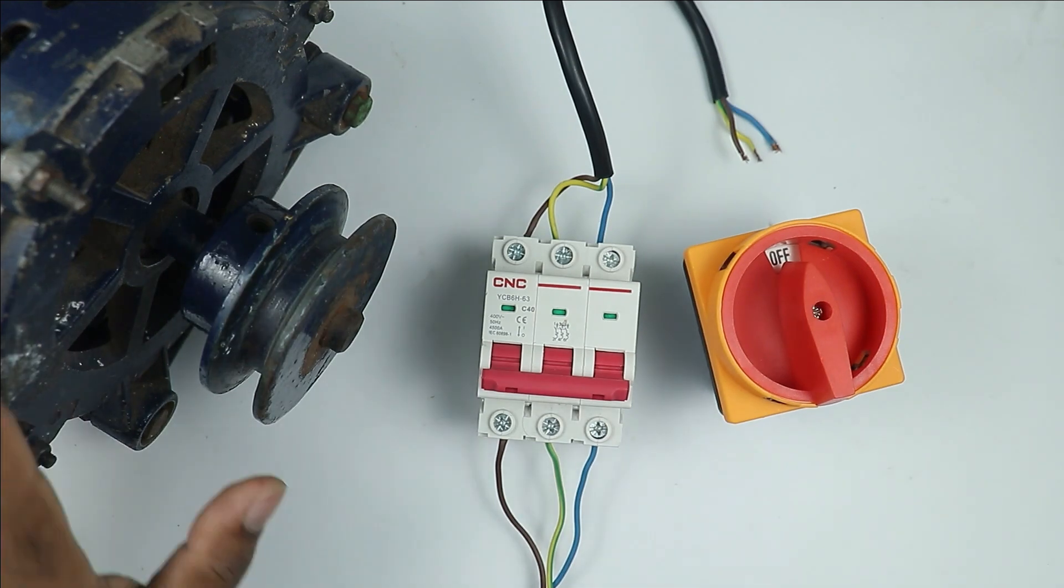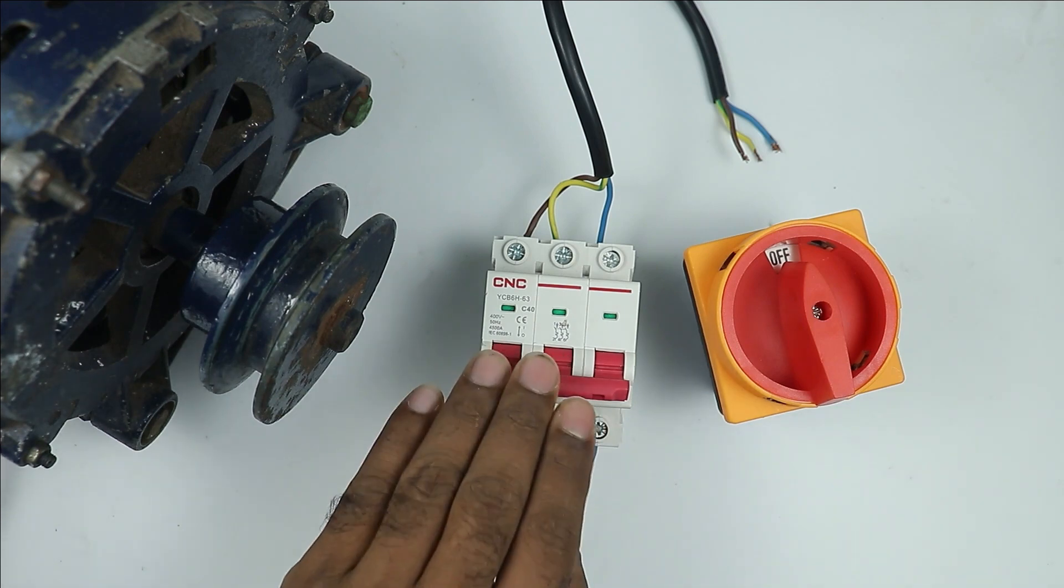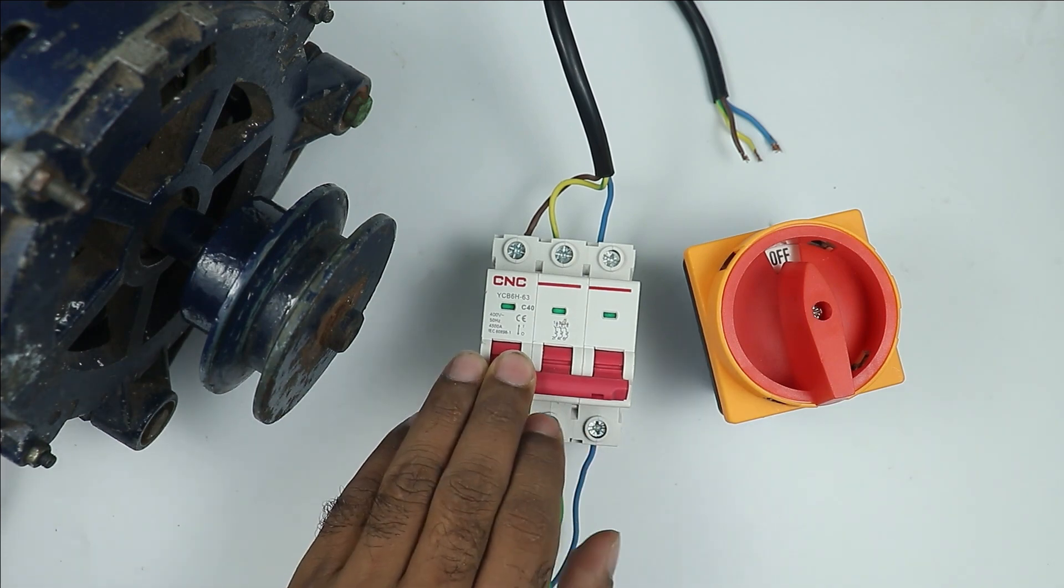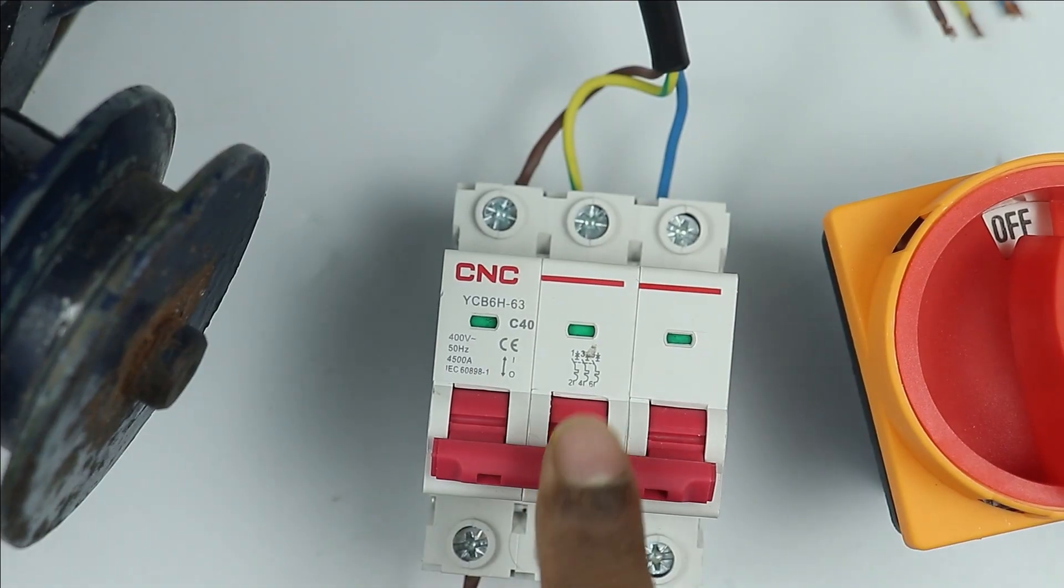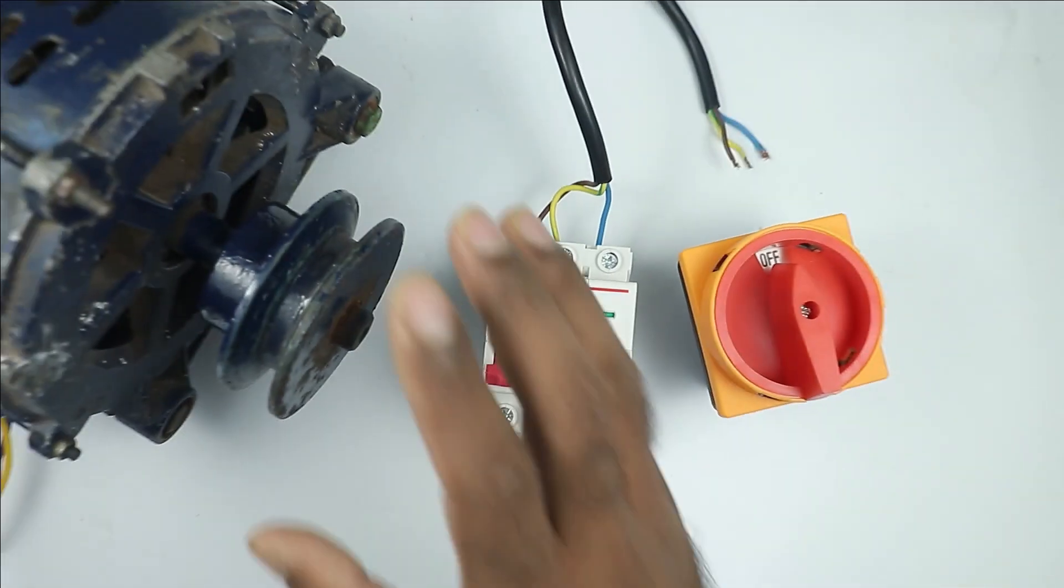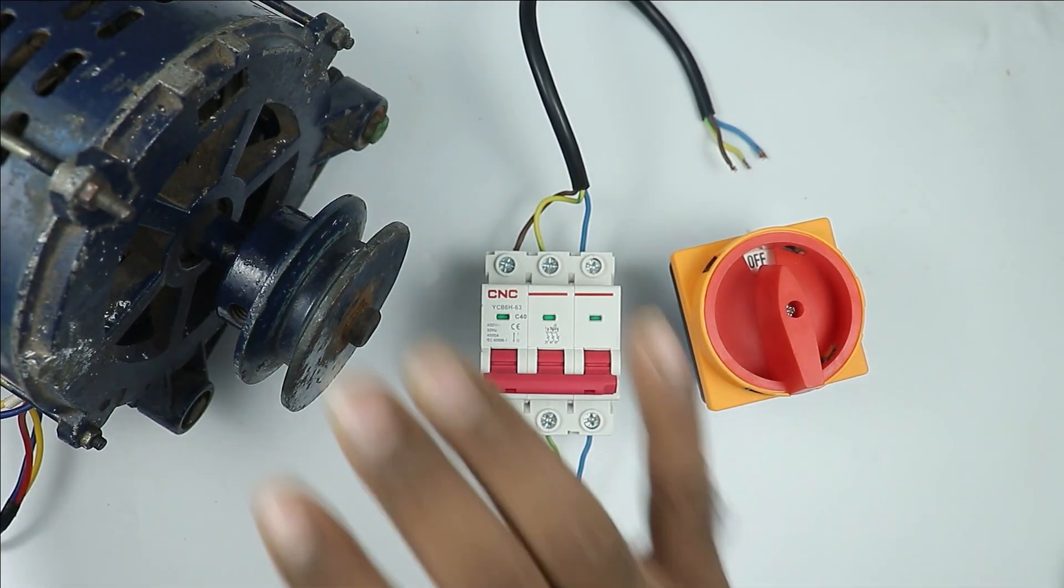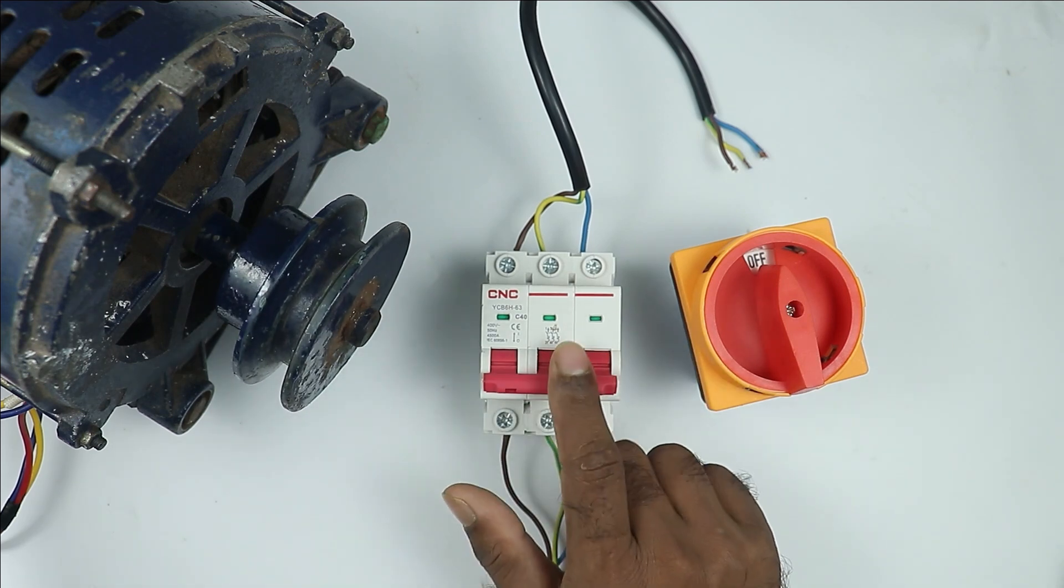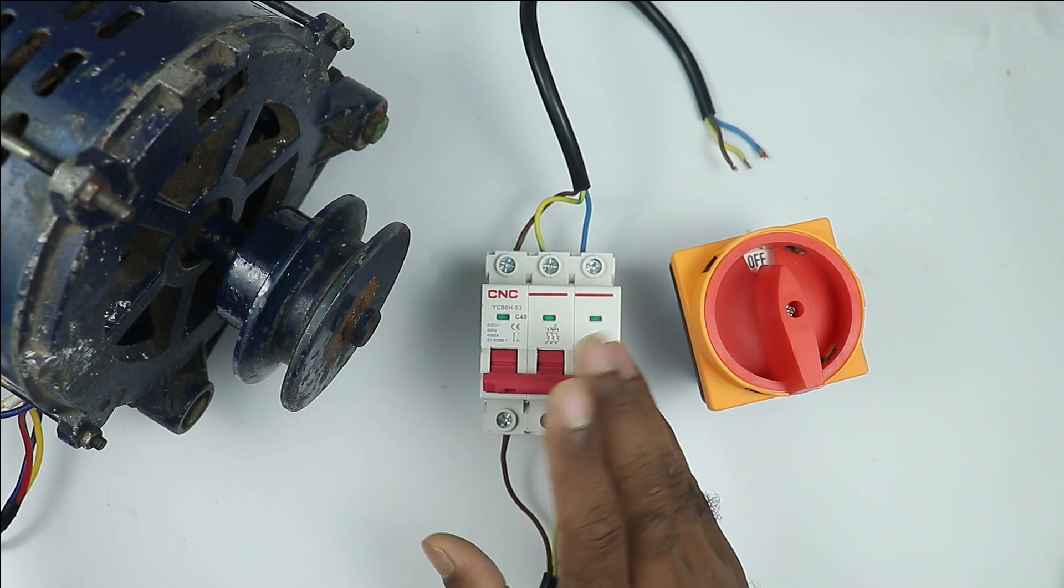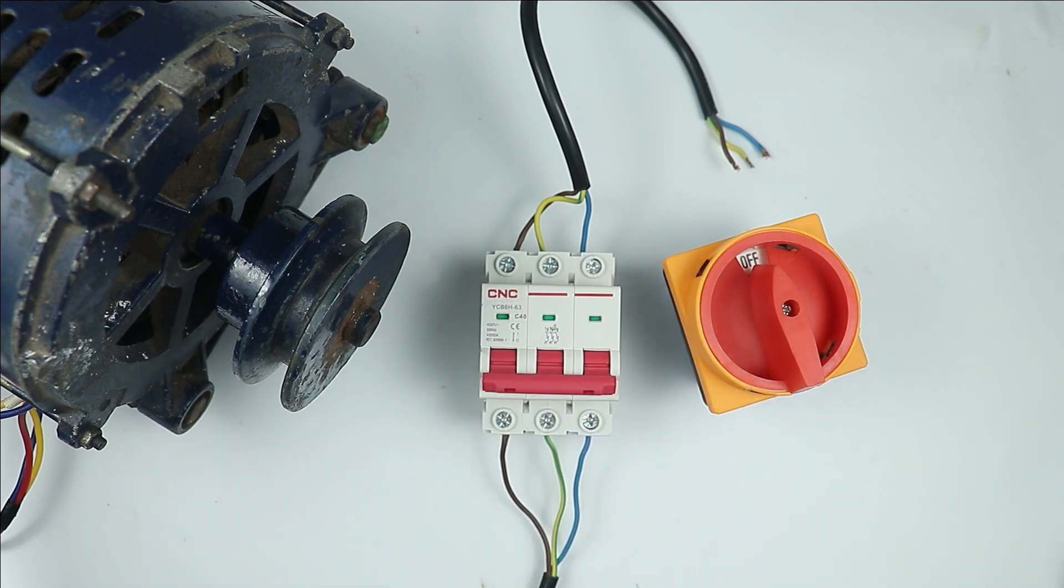If you use MCB, then your motor will be protected from overload and short circuit. But one thing you must keep in mind: the current rating of MCB must be little more than motor. You can see here, the MCB I have has a current rating of 40A and the motor is just 3 to 4A. So just for 3 to 4A, do not use 40A MCB. I used this here just to show you how it works. So I connected all three wires at the output terminals of MCB.